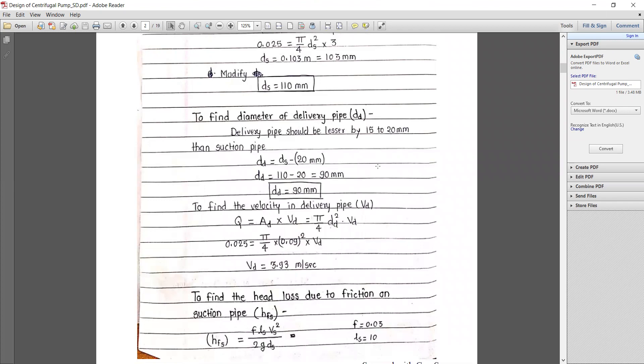For the delivery pipe, it is assumed that the delivery pipe should be 15 to 20 mm smaller in size than the suction pipe, because the suction head is always less and delivery head is always more. To maintain the required pressure and deliver the required discharge at the right quantity and time, we need to reduce the pipe diameter so that sufficient pressure is built up.